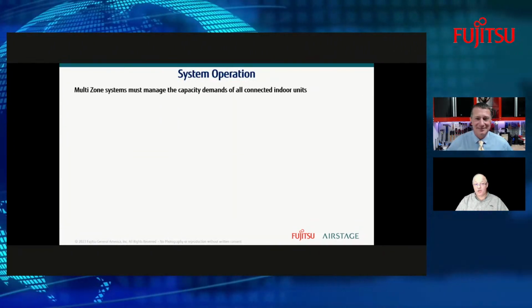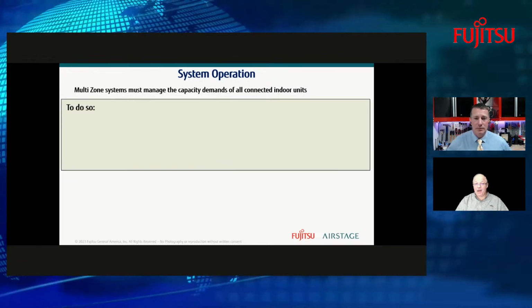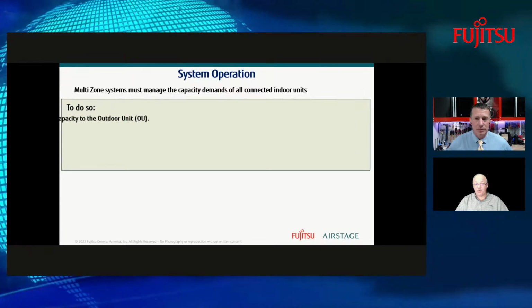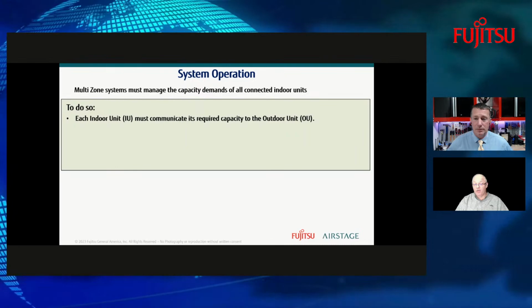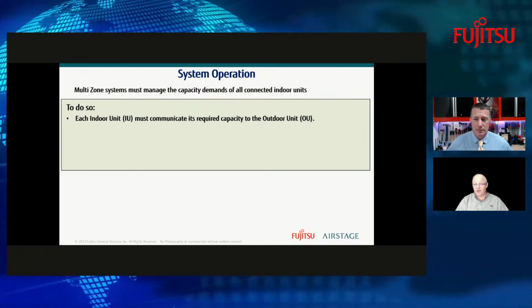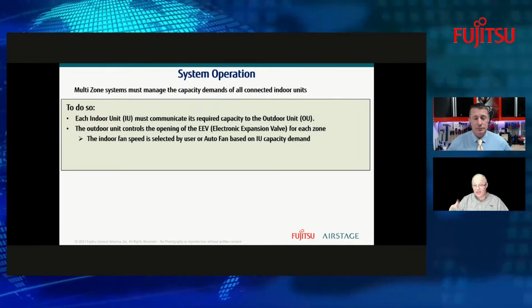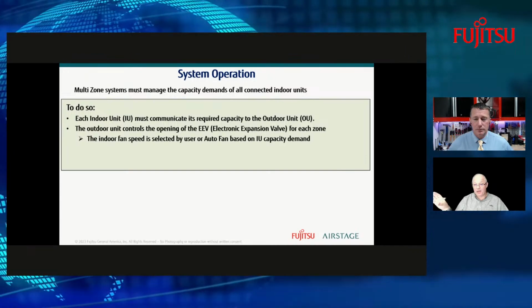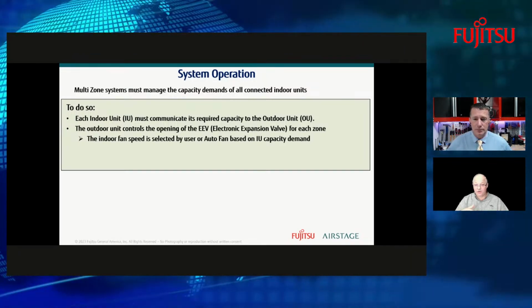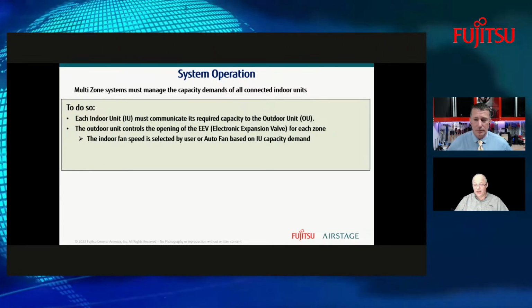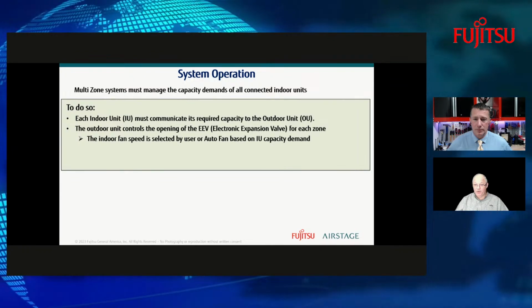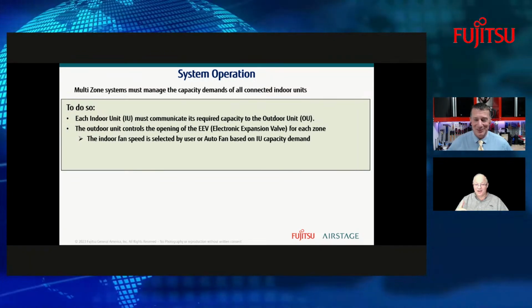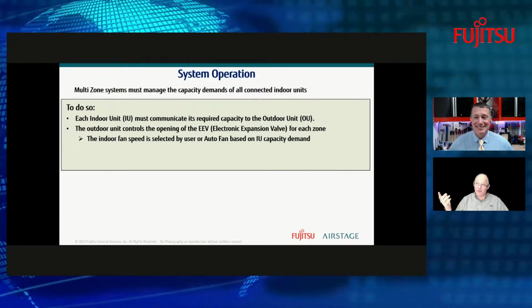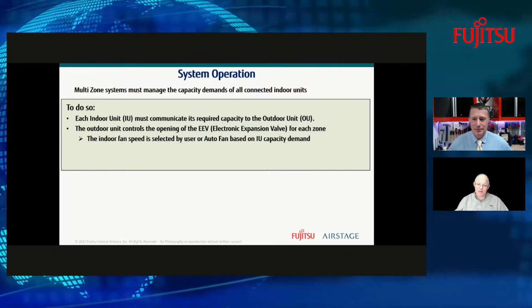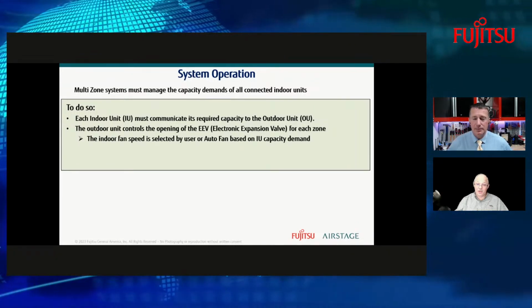All right, so let's look at the overall system operation. When you start getting into multi-zones, they're going to manage capacity demands differently with each indoor unit depending on where they're at. All the indoor units are communicating their capacity to the outdoor unit. The outdoor unit, again, has an EEV for each of the indoor units. So depending on whether it's the family room or your office downstairs or whatever, like in my office here at the house downstairs, I've got multiple computers, multiple monitors. You've seen those earlier when we were talking. This little room gets warm. Well, a lot of heat. So in my case, I'm going to end up putting a little 9K mini split into this office. So I can control it.